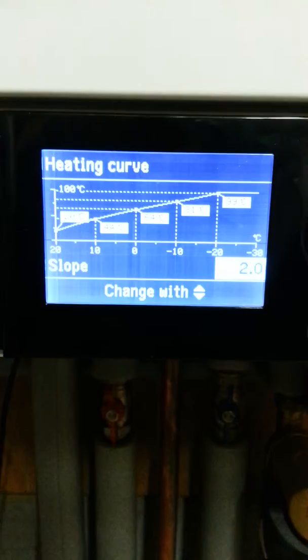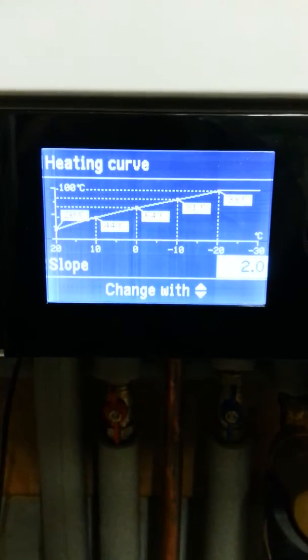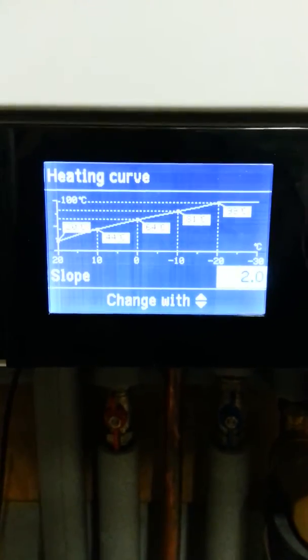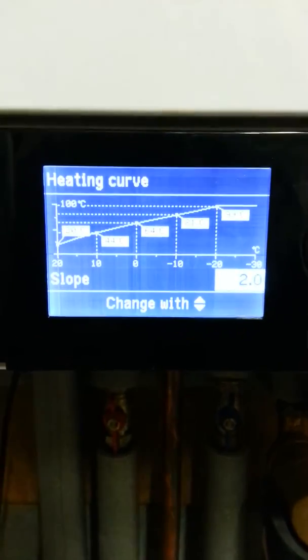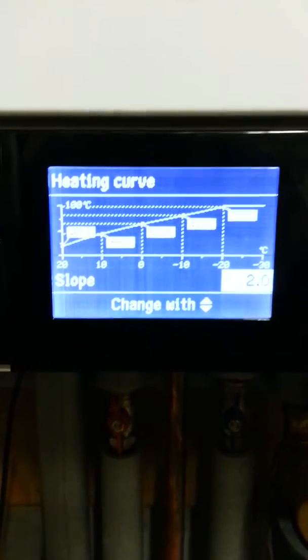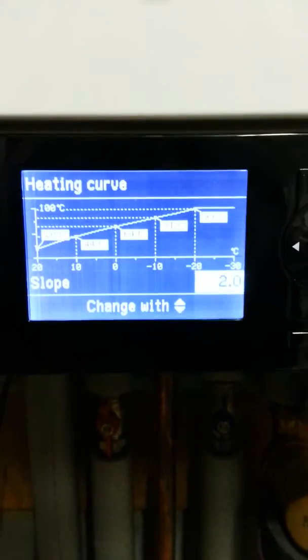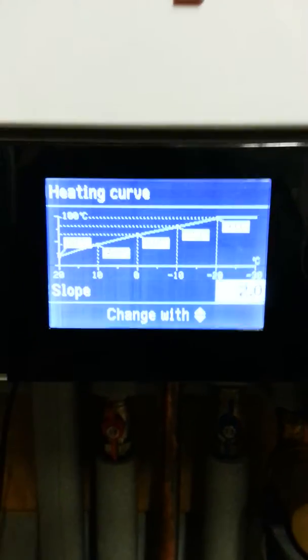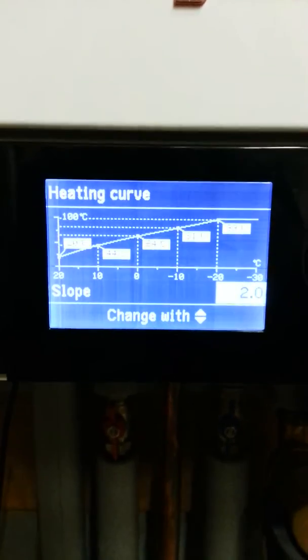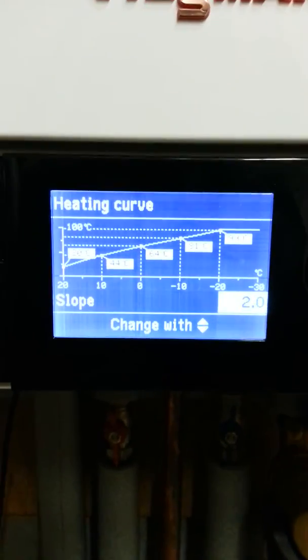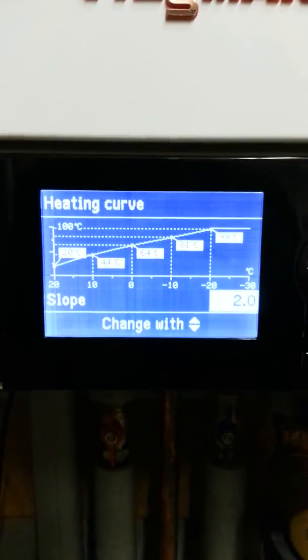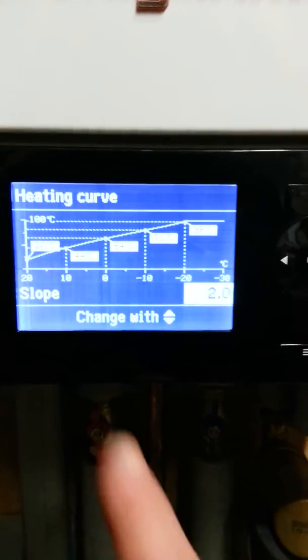At 64 flow, we'd have a 44 return. So we'd still be in condensing mode, but not fully condensing on an old Victorian house.